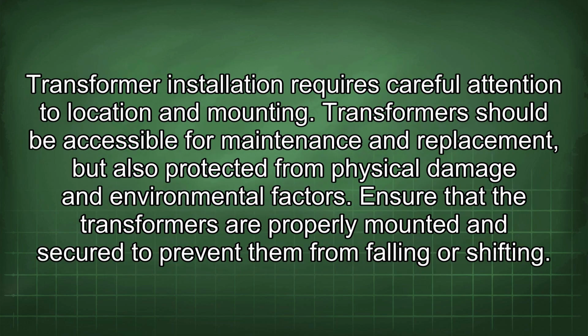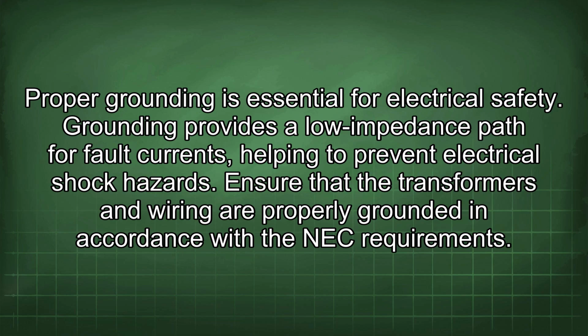Transformer installation requires careful attention to location and mounting. Transformers should be accessible for maintenance and replacement, but also protected from physical damage and environmental factors. Ensure that the transformers are properly mounted and secured to prevent them from falling or shifting. Proper grounding is essential for electrical safety. Grounding provides a low impedance path for fault currents, helping to prevent electrical shock hazards. Ensure that the transformers and wiring are properly grounded in accordance with the NEC requirements.